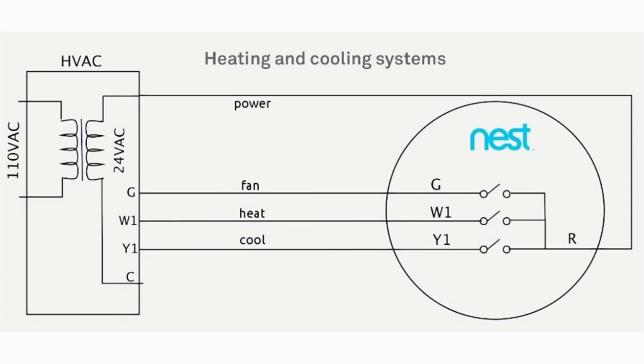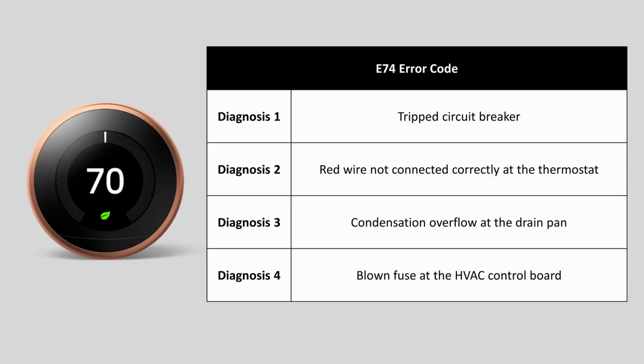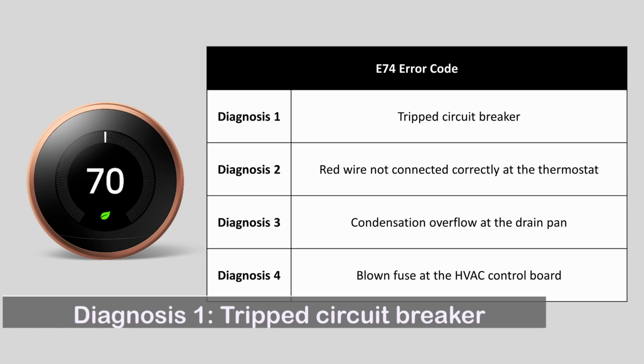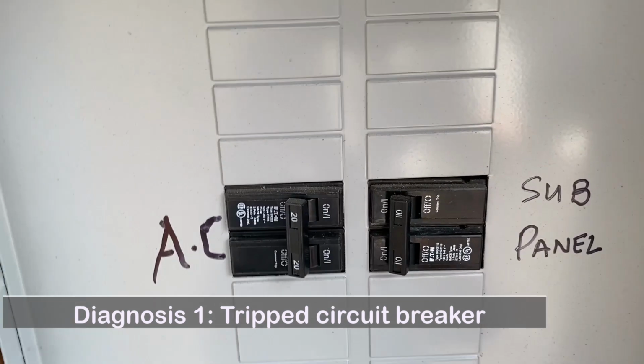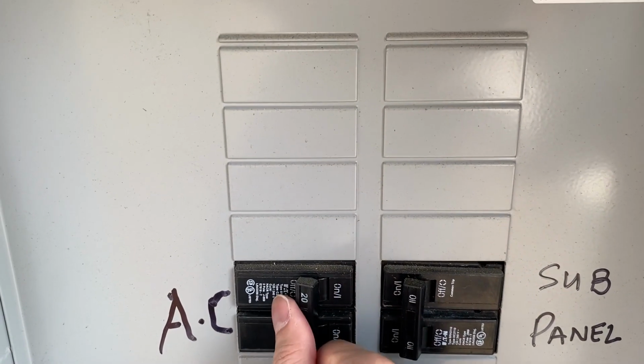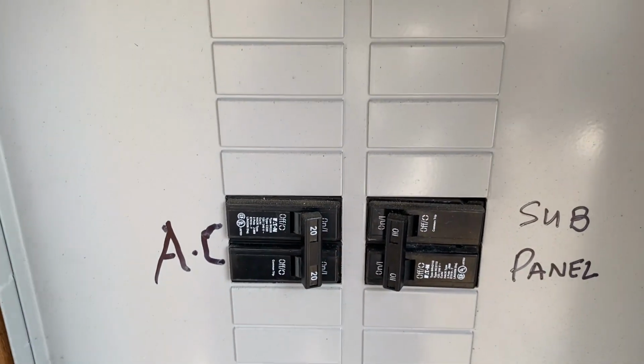Therefore, if there is no power in the red wire, the entire HVAC system, including heating, cooling, and fan, will stop working. Here are the possible reasons that can cause this error code. Diagnosis 1. Tripped circuit breaker. Check circuit breakers to your HVAC system to make sure they are at the on position.